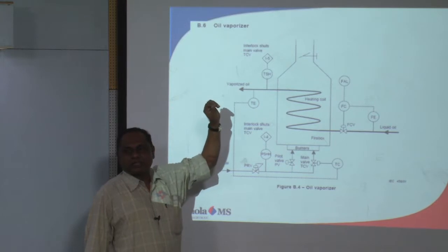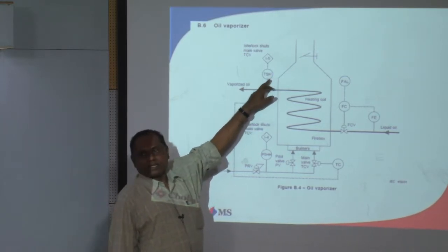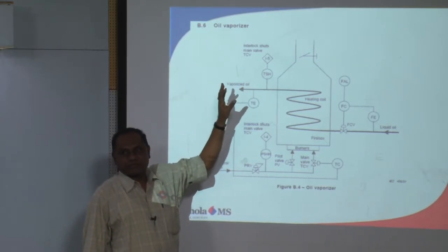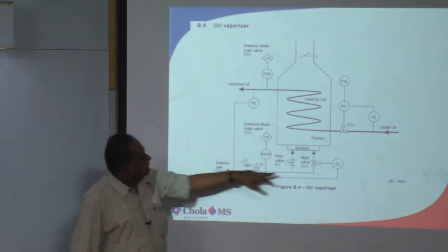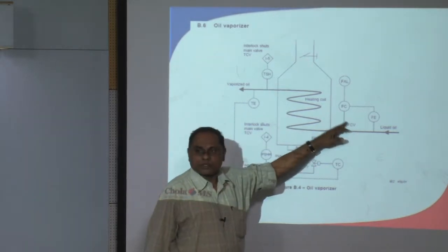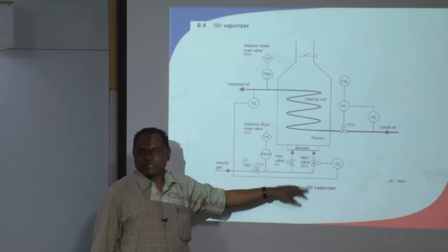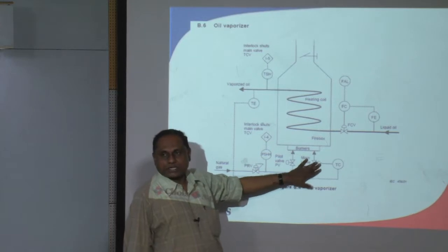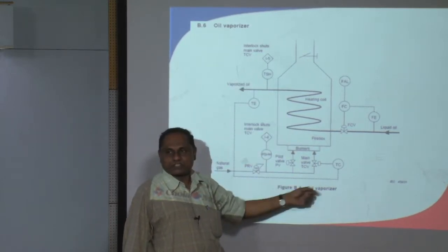Temperature switch. Okay, so say if it goes to 310, this temperature switch will sense it and cut off. It will cut off what? It should either cut off this incoming flow, or it should cut off this feeder. Otherwise, the temperature will keep rising. Okay, in case it reaches 310 degrees, it's cutting off only the gas flow. This is only heating it.